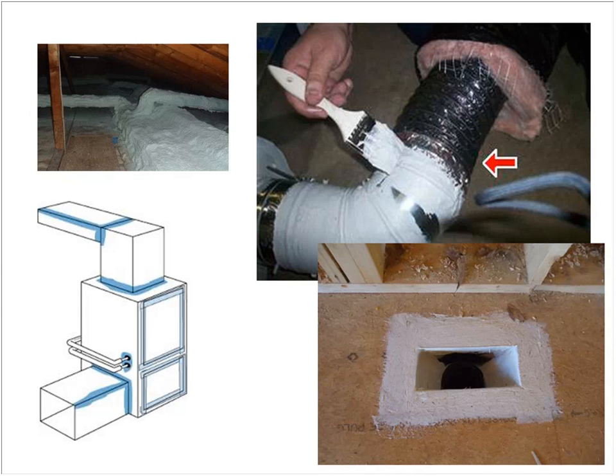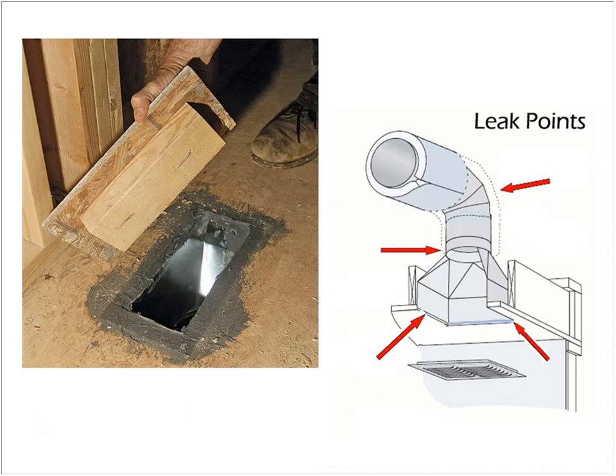And then on the bottom right-hand corner, that is a penetration that's coming through a floor of an unconditioned crawl space. And you can see that they have used mastic and caulking around the transition boot at the OSB, and then they seal it with a mastic around the top so that there's no leakage between the transition housing and the floor material that might sneak past a sealed register grill. There's another floor connection on the bottom left.